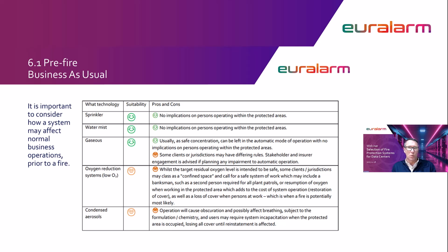Added to this, when major works were planned in the area, full oxygen was restored, and so after works, when fire is possibly of greatest likelihood, there was a period of no protection until the system was able to get down to the target oxygen level. That's just one example.